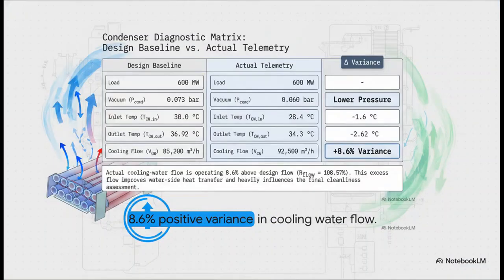Let's see how this telemetry builds out our diagnostic matrix. Here, we're contrasting the theoretical design baseline against our actual unit telemetry, both stabilized at a 600 megawatt load. As you can see, our actual vacuum is sitting nicely at a lower pressure of 0.060 bar. But look at the bottom row, the cooling flow. The actual telemetry is showing 92,500 cubic meters per hour. Guys, that's an 8.6% positive variance above the design flow. The crucial takeaway here is that this excess flow massively improves waterside heat transfer, and it's going to heavily influence the rest of the math we're about to do.